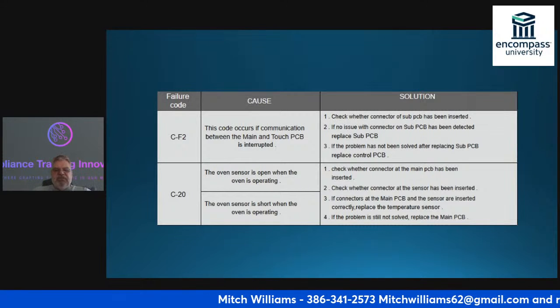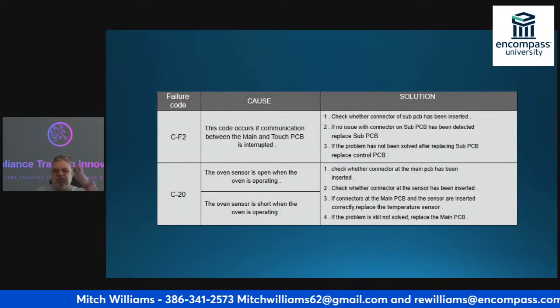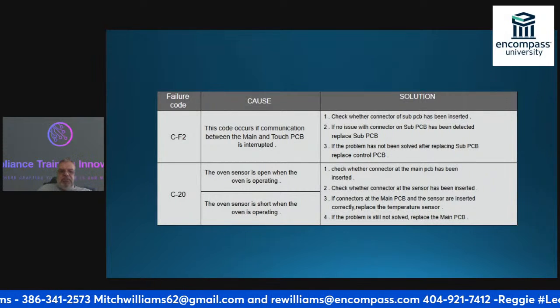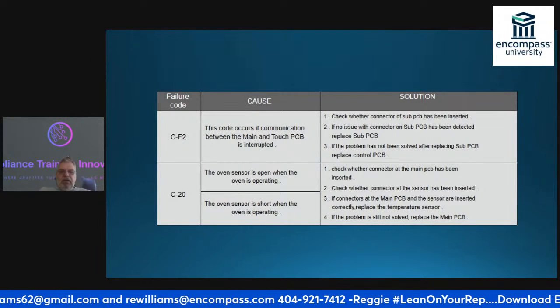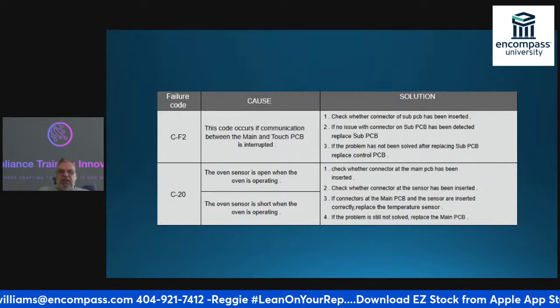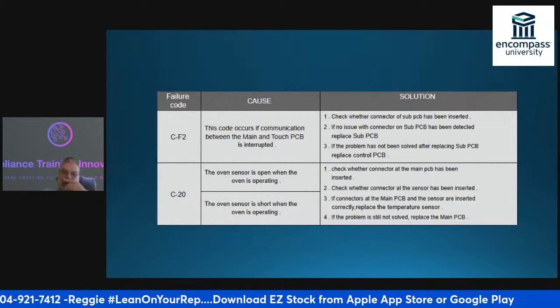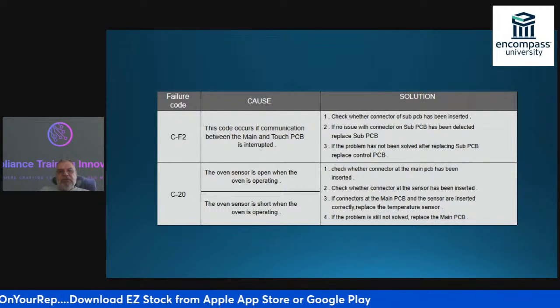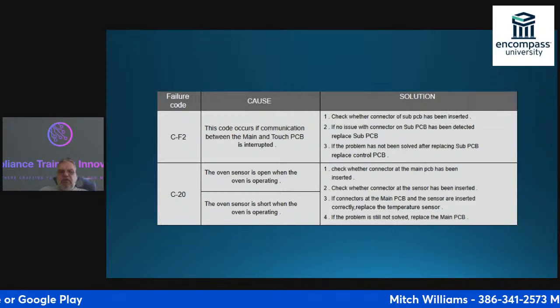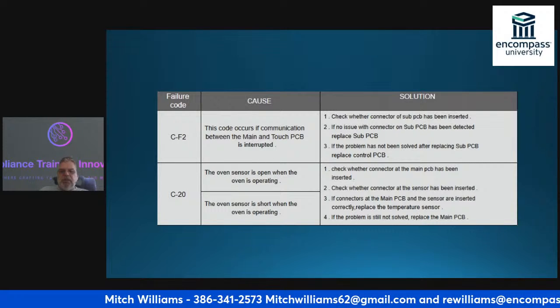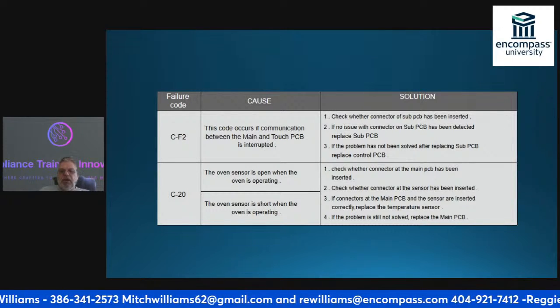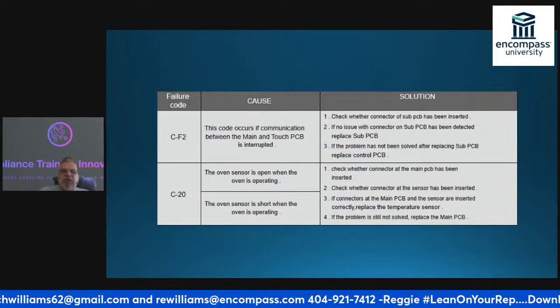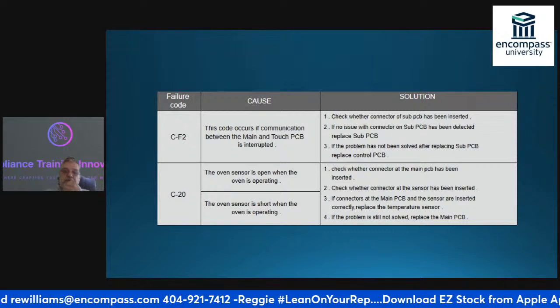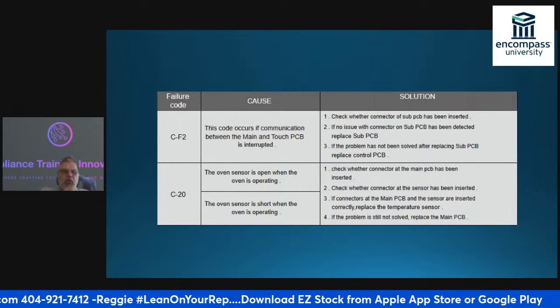If I have a CF2, this occurs when communication between the main PCB and the touch PCB is interrupted. Could be a power failure, so I'm going to check that, and ask the customer when's the last time they lost power, or if they were flipping breakers, that could cause this error. So I'm going to check the connector for the sub PCB. If there's no issue with the connector, I'm going to replace the sub PCB. If the problem isn't solved after that, I'm going to replace the control PCB.